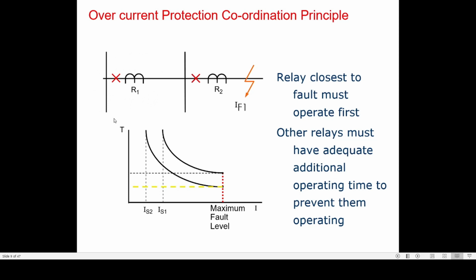But we are delaying this relay to operate for 200 millisecond. That means for a fault which has higher magnitude, the relay will operate at larger time intervals. That means the fault which is closer to the source will be cleared in more time as compared to the faults away from the source. So this is again causing a problem.